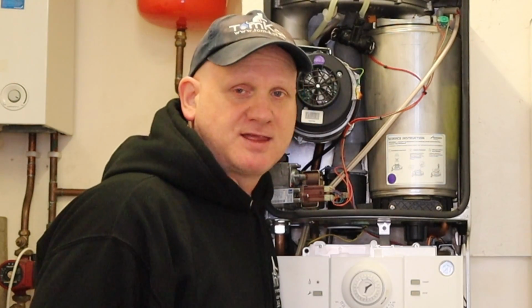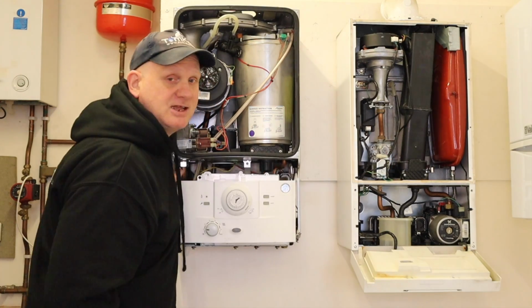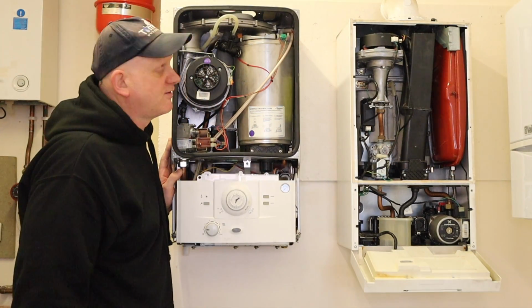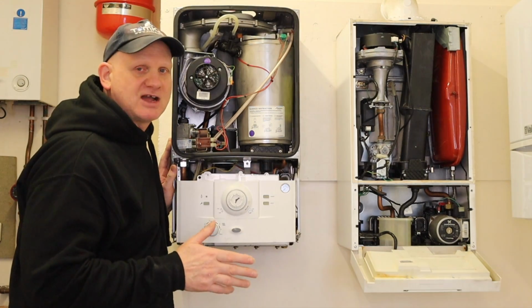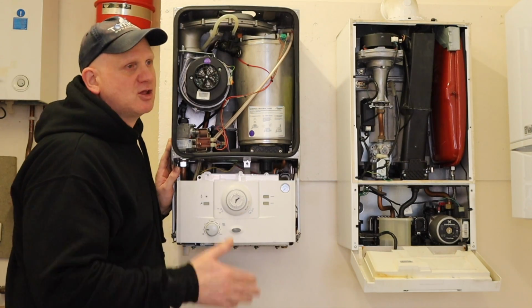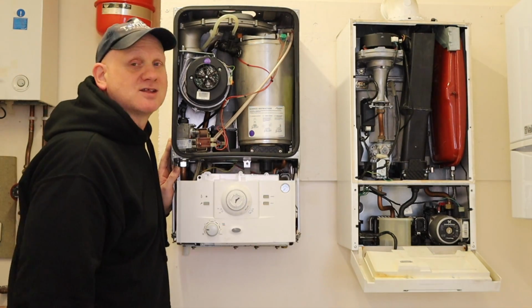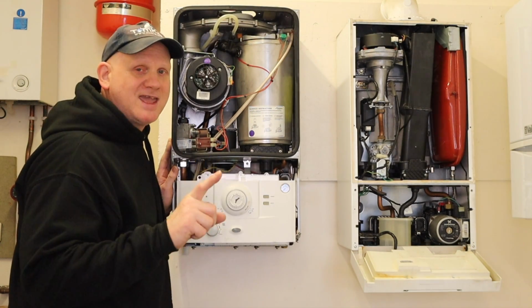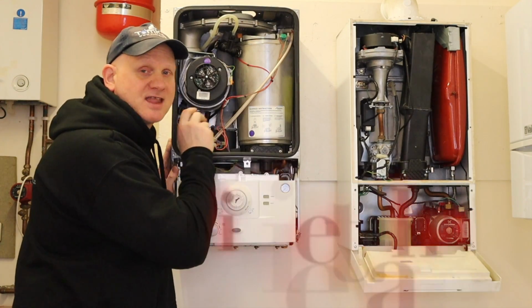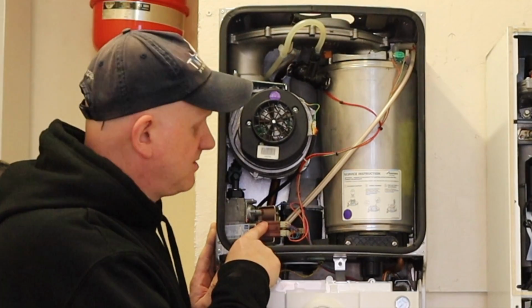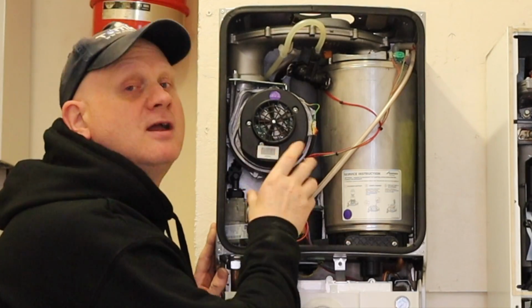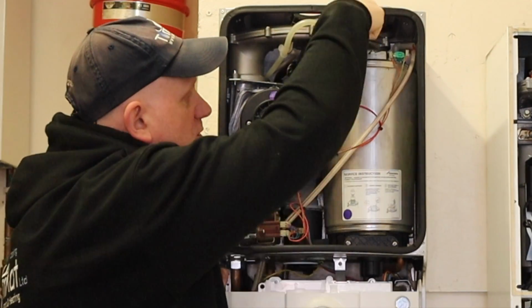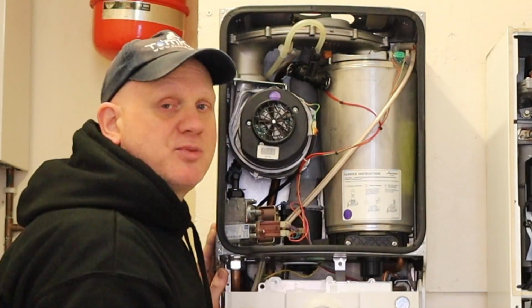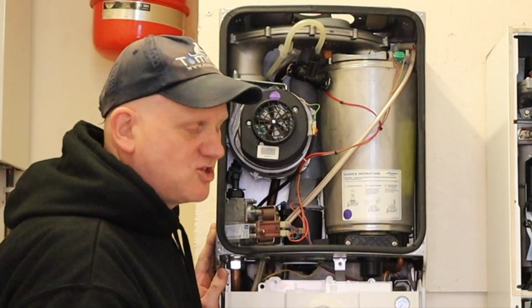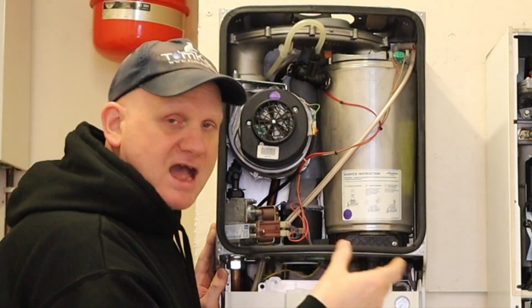Now let's talk about aluminium heat exchangers. Now the two boilers we can see here, this is an Ideal boiler and this is a Worcester boiler, both have aluminium heat exchangers. Now most of the boiler manufacturers do have a range of aluminium heat exchangers. Some only have aluminium, some have aluminium and stainless steel heat exchangers. It depends on the manufacturer. Now this one has a stainless steel outer but actually is an aluminium heat exchanger, this Worcester. So what happens is the gas comes into the gas valve, the fan then sucks the gas out, mixes it with air, and blends it into this tube, which then comes into a burner, which then forces the products of combustion, the POCs, down through the heat exchanger, which takes out all that heat, which then turns it into carbon dioxide and water vapour.